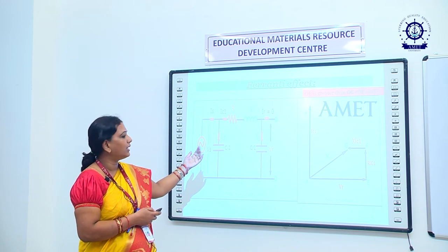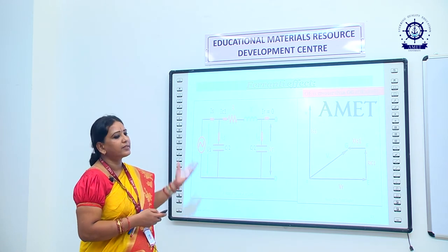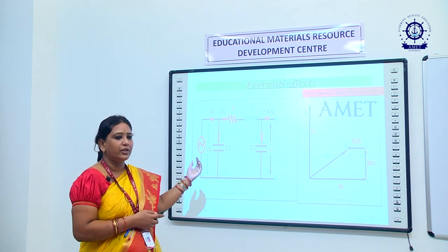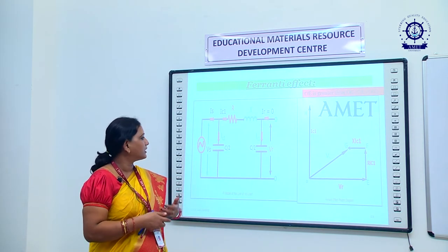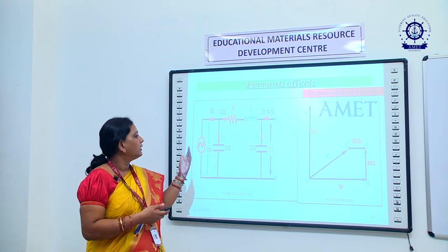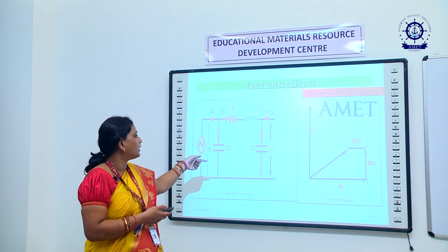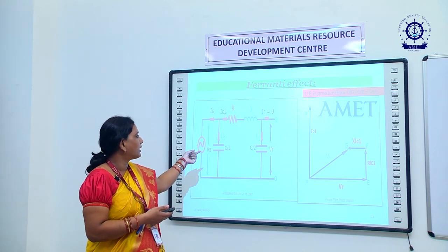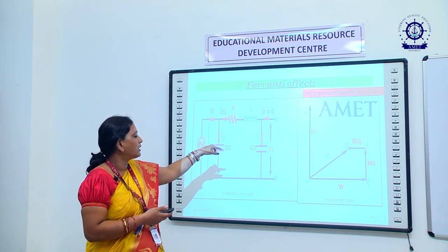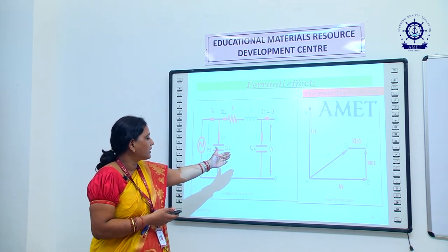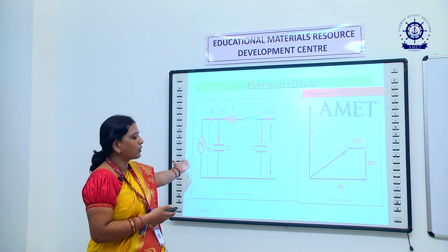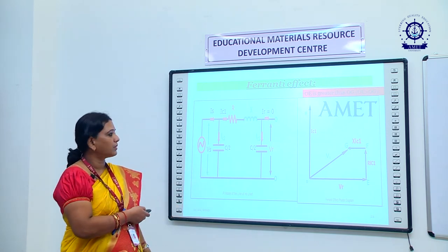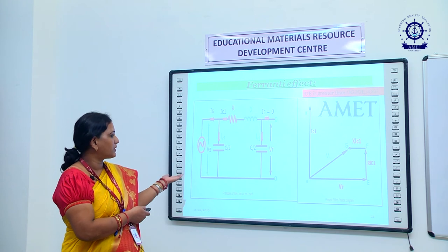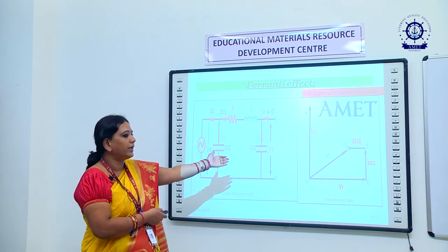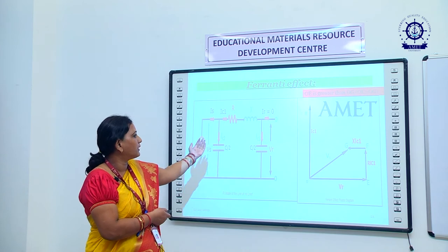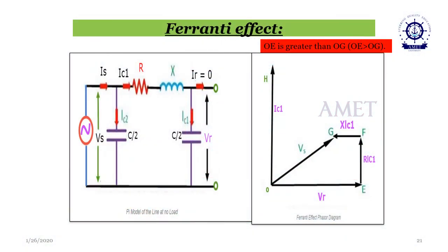So the capacitor automatically acts as a source, because it is an energy storing element, and it starts generating more reactive power, and in turn generates more current. That high current circulates into the network, and when it circulates, there will automatically be a generation of overvoltage on the receiving end side, so the sending end side appears reduced. So this has to be quantified, or it has to be suppressed. How to do that? By connecting an inductor, so that the excess energy is absorbed. In that way we can maintain the balance in the system.